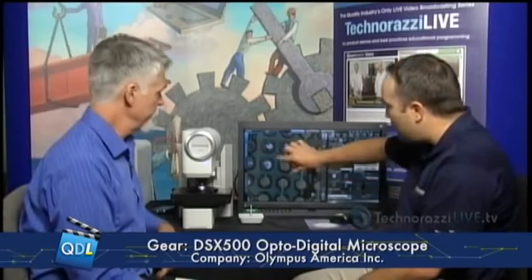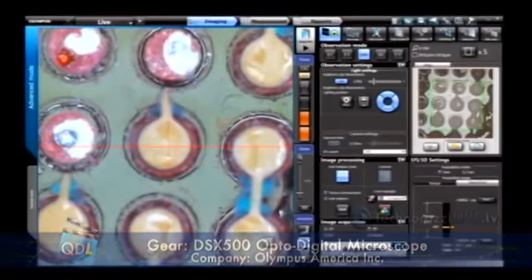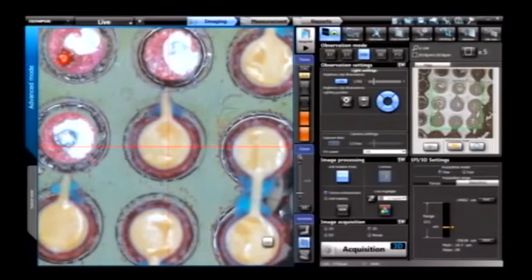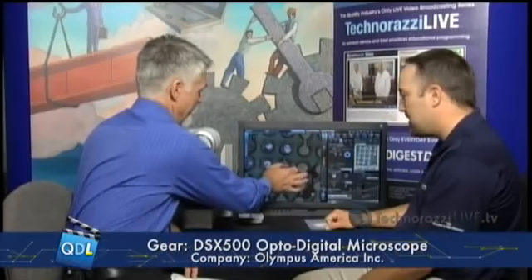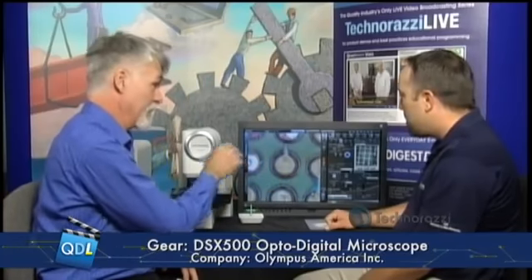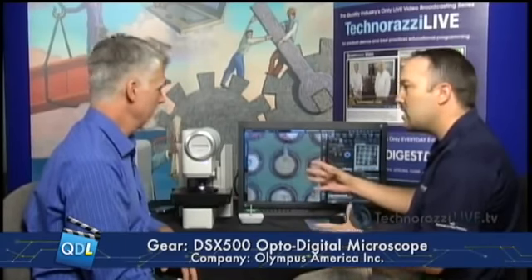So on the touch screen, we have a built-in optical zoom feature. Now this is interesting. I noticed you pinch to zoom. If you've got an iPhone or iPad or that type of thing, this works kind of the same way. And you're actually controlling the optics when you do that. The optical zoom is built in, yeah. So you're not digitally zooming. You're not losing resolution. We can optically zoom up quite a ways to get very high magnification ranges by using just one objective. We do still use our world-class optics from Olympus. We can use our entire range of UIS-2 optics, and Olympus did specifically design lenses for this microscope as well.